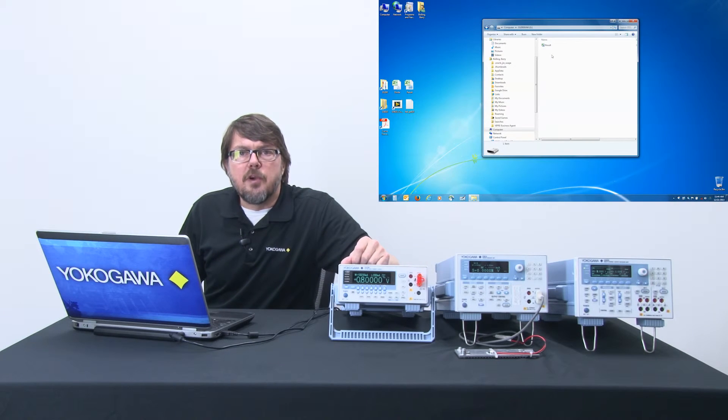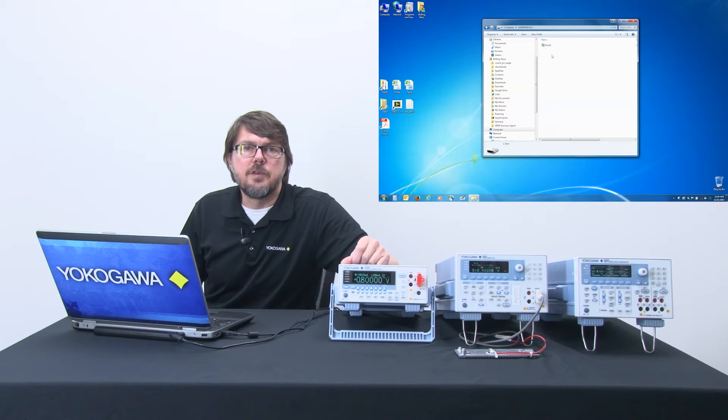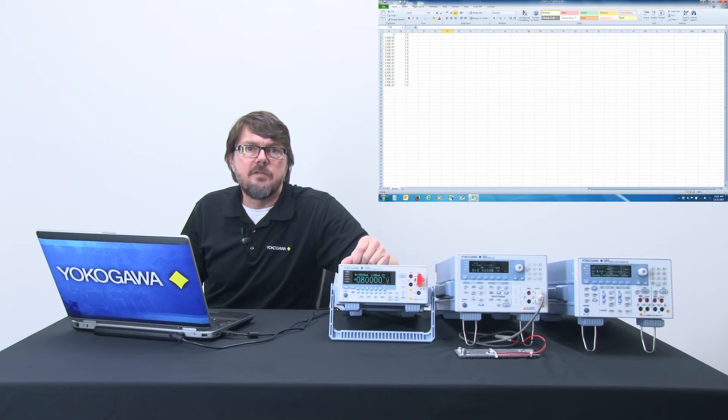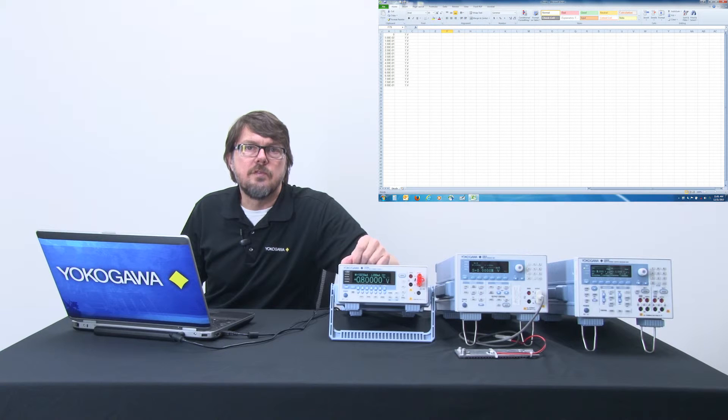First, I load the program, which is nothing more than a CSV file containing a list of voltage values that we want the SMU to play back. Here is the CSV file opened within Excel. Three columns, each has value, range, and source type, either a voltage source or a current source. It is that simple.